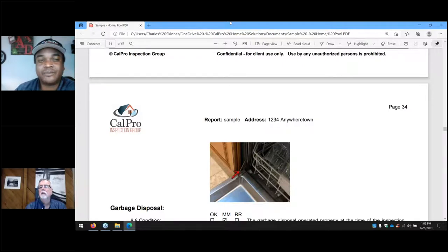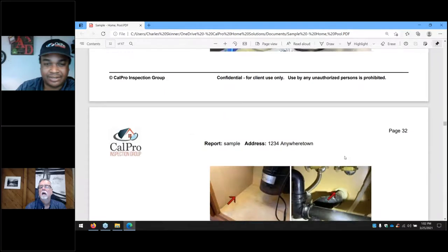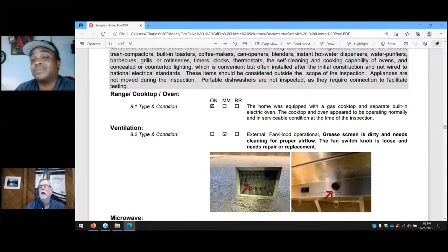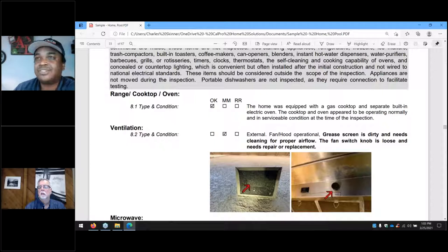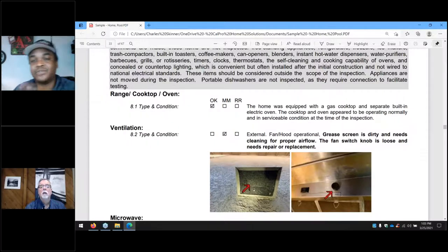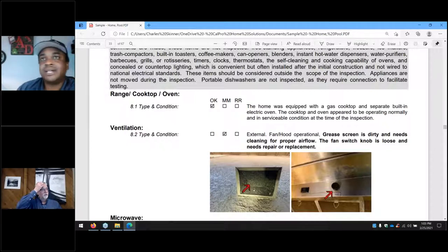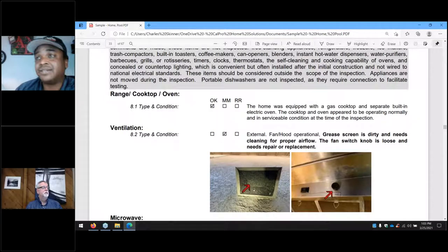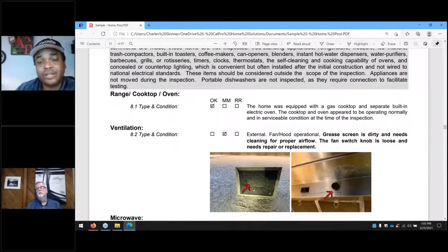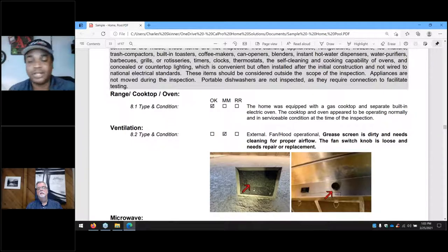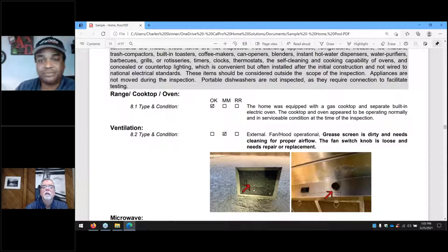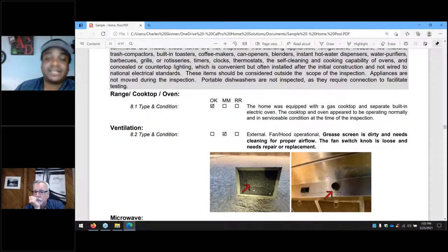Burners that aren't cleaned, when you turn them all the way to low, can either not ignite properly or go out entirely — leaving gas just flowing. If you're trying to simmer something and the flame goes out, that's a safety risk and a red item on our reports. For ventilation, dirty grease screens, light bulbs that are out, and poor operating fans are typical issues. Microwaves are tested for operation — usually it's just dirty grease screens, non-working light bulbs, or a turntable that doesn't function.